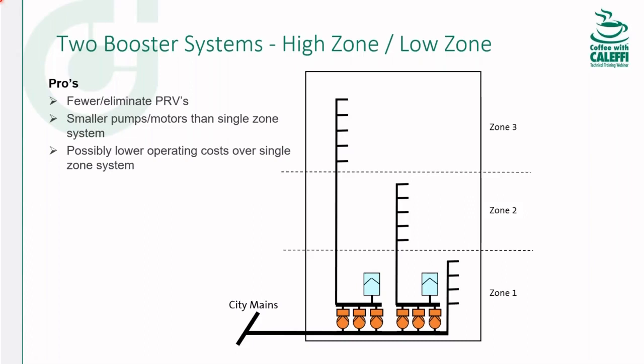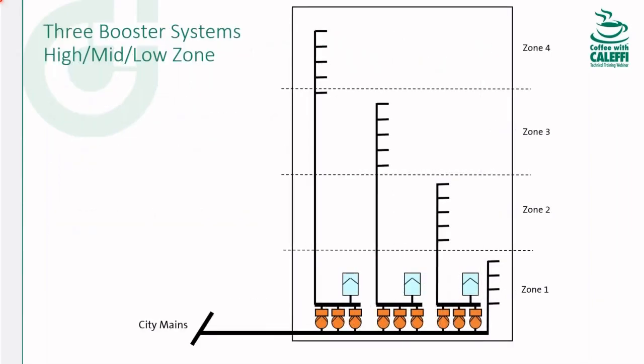However, you end up with more risers. So the cost savings with the pressure regulator valves and the added piping may be a wash there. But this has been done with high rise design, and it's always a choice out there to use it or not. So this is an option that's available. It will almost always result in energy savings, but you have to weigh that with the installation cost. So somebody that's doing the project has to crunch all the numbers in the beginning. Because the pros we mentioned, the cons is that it's a higher price and other things like that.